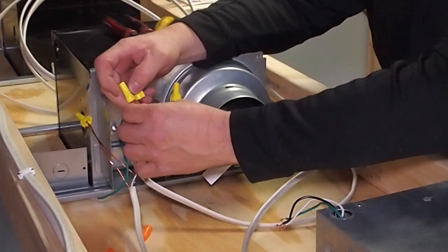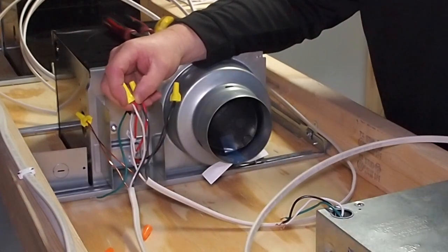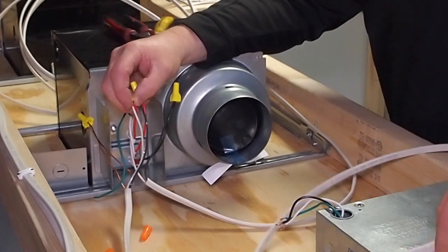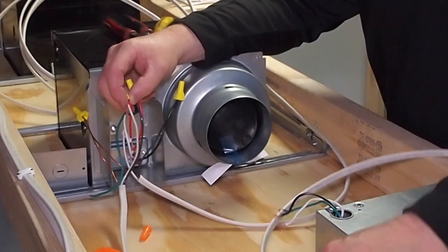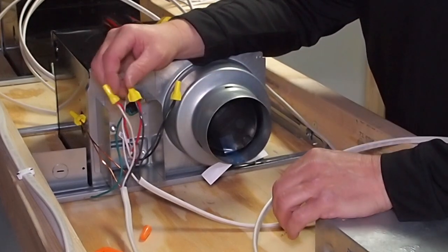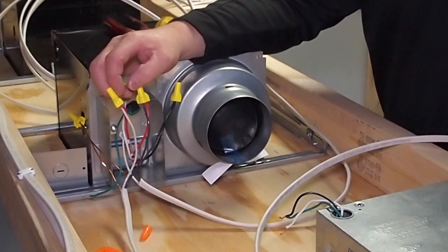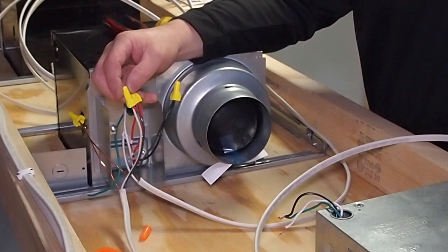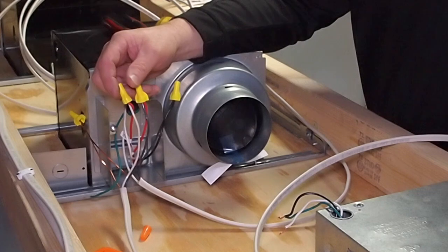The two red signal wires. We are using the old wire that went down to the switch box. We disconnected power so there is no voltage on this. We are just making or breaking some kind of a contact in here. That is going to allow that fan to ramp up to do your spot ventilation of either 50 or 80 or 110 CFM. Whichever you choose to select.